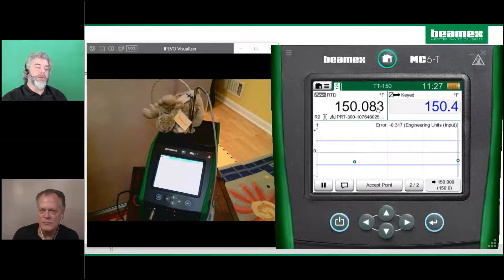Okay, thanks, Roy. So the stability is still below 1. But for brevity here, let's go ahead and accept this. It's warning us that we're cutting a corner. But everything passed. So this is the summary for the temperature element and the transmitter, where we're checking the temperature versus the milliamps. We had a maximum error of under 0.3 degrees.